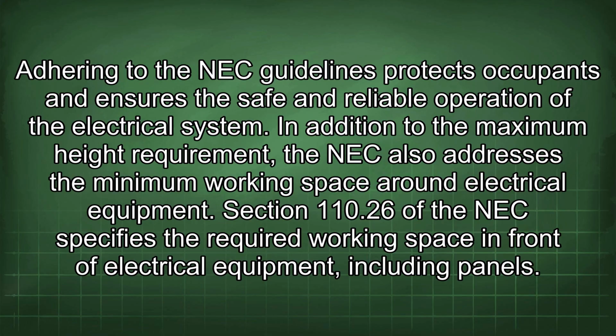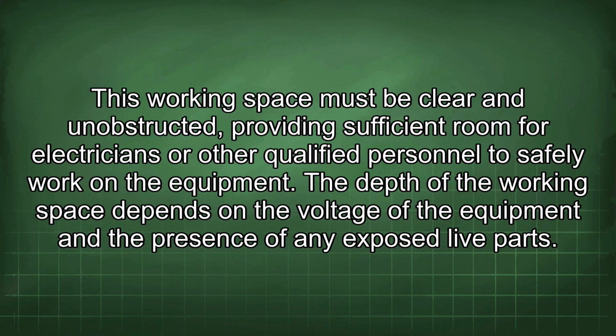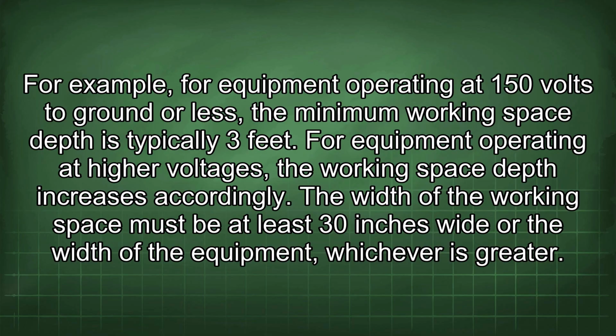In addition to the maximum height requirement, the NEC also addresses the minimum working space around electrical equipment. Section 110.26 of the NEC specifies the required working space in front of electrical equipment, including panels. This working space must be clear and unobstructed, providing sufficient room for electricians or other qualified personnel to safely work on the equipment. The depth of the working space depends on the voltage of the equipment and the presence of any exposed live parts. For example, for equipment operating at 150 volts to ground or less, the minimum working space depth is typically 3 feet. For equipment operating at higher voltages, the working space depth increases accordingly.